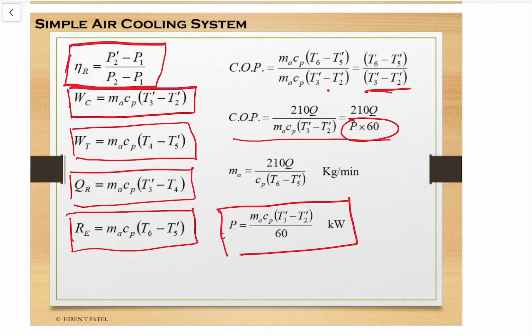Ma is the amount of air passing from the cabin, or the amount of air required to generate the refrigerating effect, that is Ma is equal to 210Q divided by Cp T6 minus T5 dash, in kg per minute.